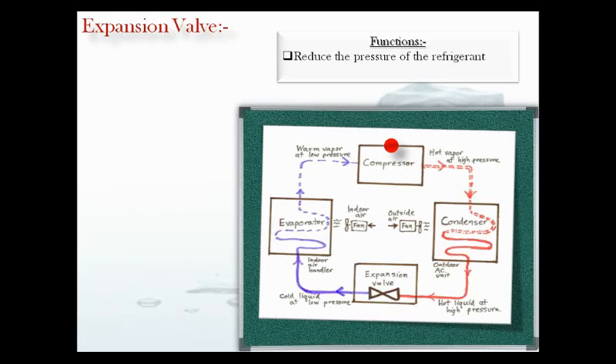The second function of a thermostatic expansion valve is to keep the evaporator active. The TEV allows the flow of refrigerant as per the cooling load. At higher load, the flow of refrigerant is increased, and at lower load, the flow is reduced. It won't happen that the load on the evaporator is high while the flow of refrigerant is low, thereby reducing the capacity of the evaporator. The TEV constantly modulates the flow to maintain the superheat for which it has been adjusted.